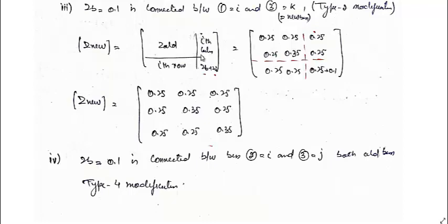Now the ith column of this is the Z old. i is equal to 1, that is 0.25, 0.25, the first column. Z old will be this, 0.25, 0.25, 0.25, and ith row, that is 0.25 and 0.25. And this will be equal to ZB plus Zii, that is 0.25 plus 0.1, that is 0.35. This is the Z new when we add this branch.